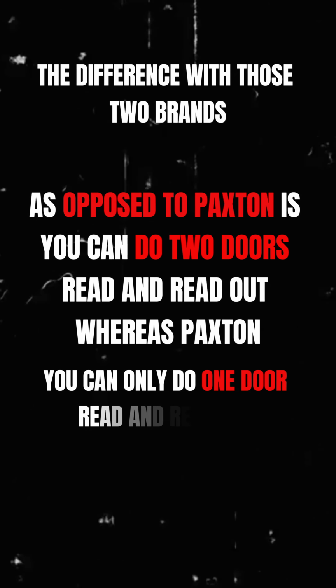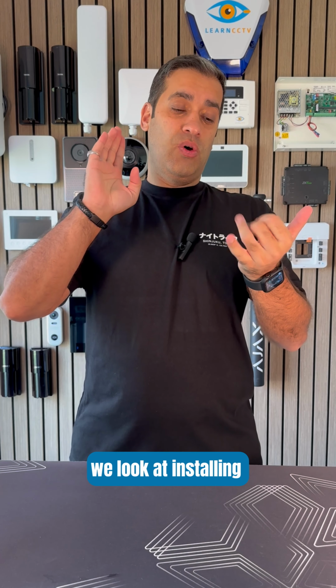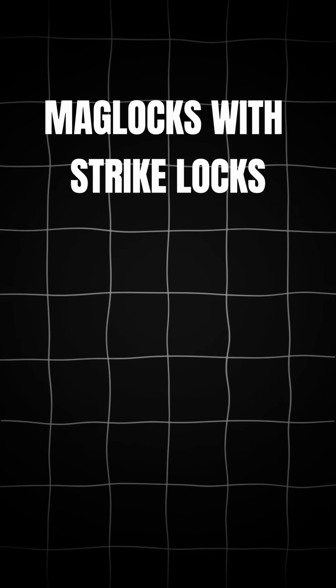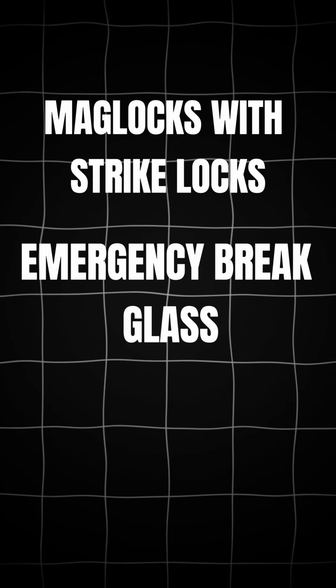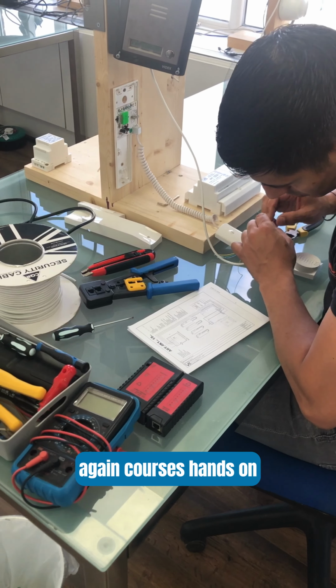Now, the difference with those two brands, as opposed to Paxton, is you can do 2 doors, read in, read out, whereas with Paxton, you can only do 1 door, read in, read out. We look at installing mag locks with strike locks, emergency break glass, push to exits, and again, the course is hands-on.